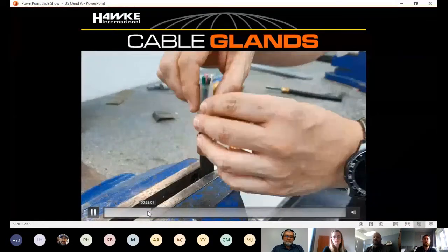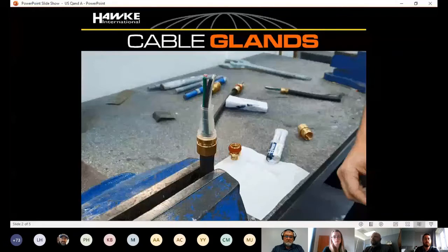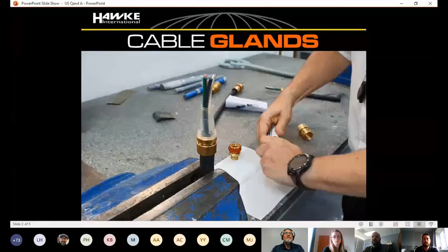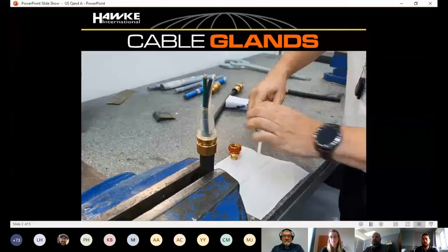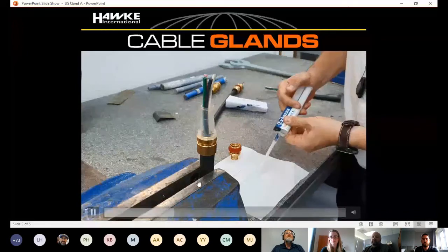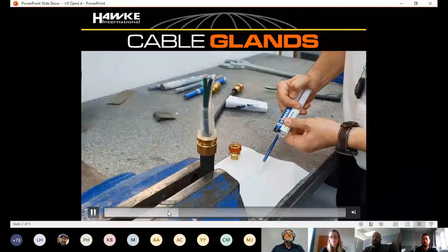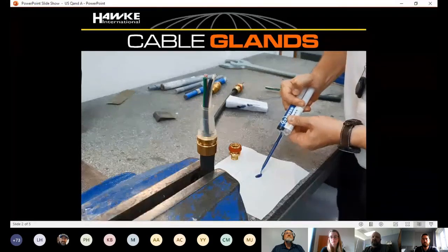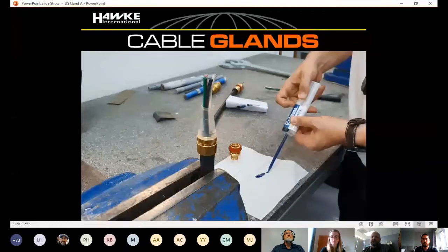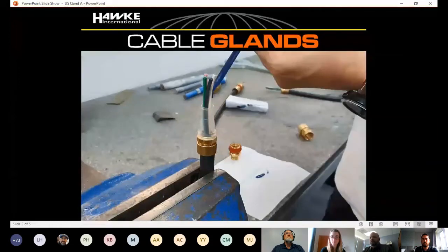And then the other option, which Matt has alluded to, is the injectable resin. It makes it very simple to do your installation, and there's a temperature chart associated with the cure times. What I've seen here in the Gulf Coast, and even on the East and West Coast during the summer months, is that some of that gets to what they call a shore hardness within 15 to 20 minutes. But you obviously want to make sure that you're looking at the temperature gauges and making sure that it's properly cured before you start handling it afterwards. There are pros and cons to both.